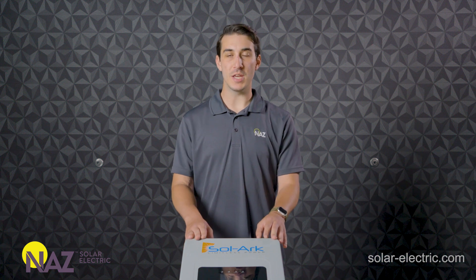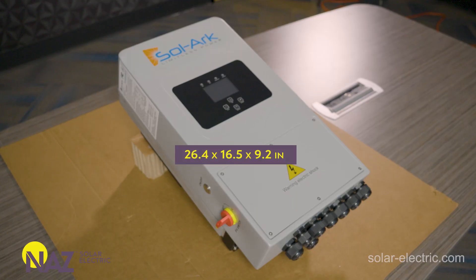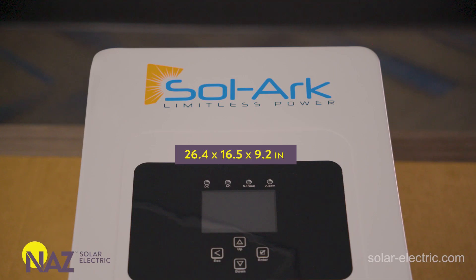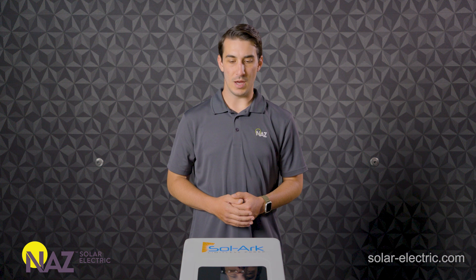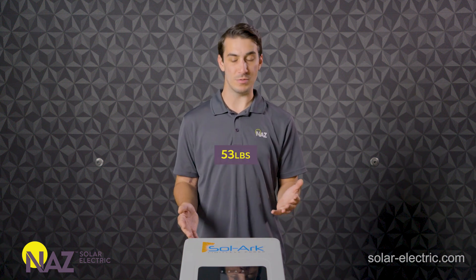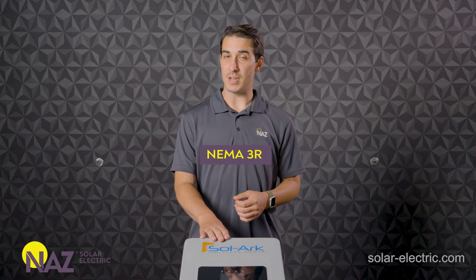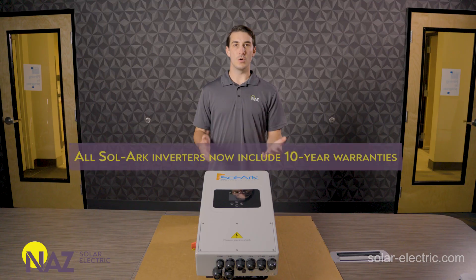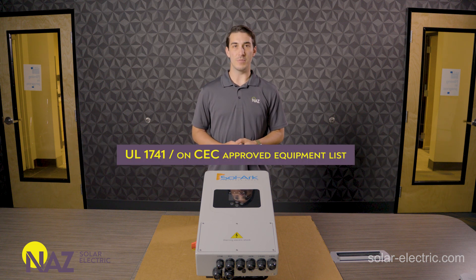As you can see, the unit on the table has a pretty compact form factor — a fairly small unit. It's about 26.5 inches tall, 16.5 inches wide, and is meant to be wall mounted, sticking out from the wall about 9.25 inches. The transformerless design of the Sol-Ark 5K means it's only 53 pounds, so very easily maneuverable by a single person. It also has a NEMA 3R rating, so it can be installed outdoors. Sol-Ark backs this product with a five-year manufacturer warranty, it has UL 1741 certification, and it is included on the CEC — the California Energy Commission — approved equipment list.